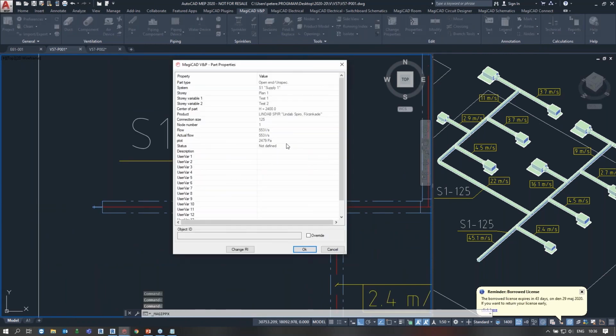Now it says the volume should be 553 liters per second, and even here I have even higher pressure than on the Revit side. Here I need a fan bringing me 2,479 pascals to squeeze this amount of air into this 125 size duct.